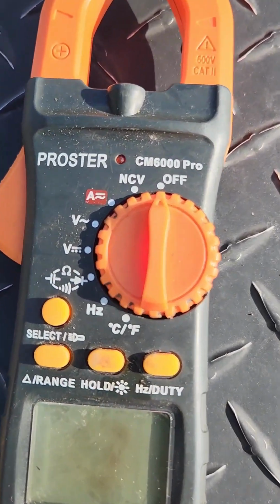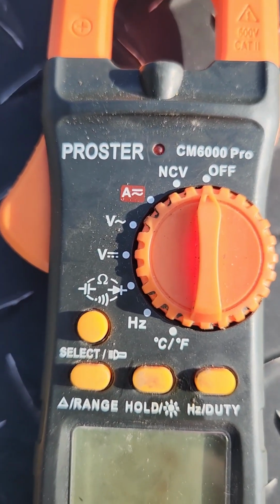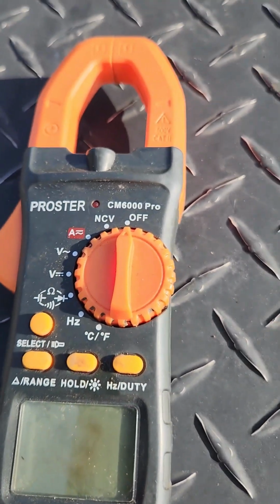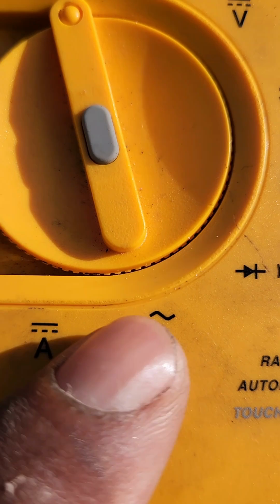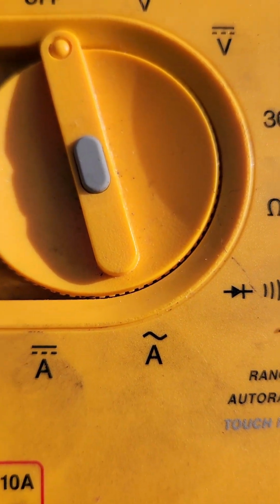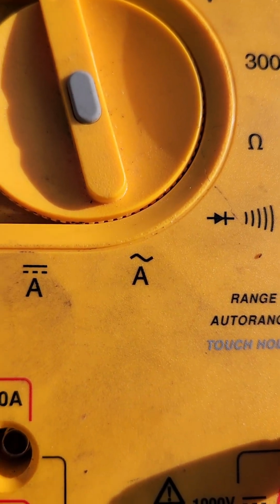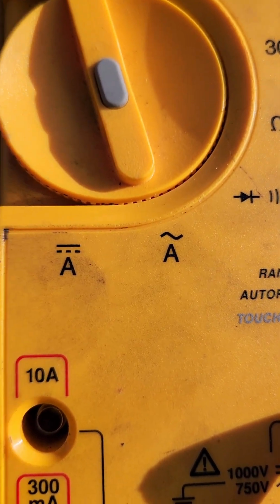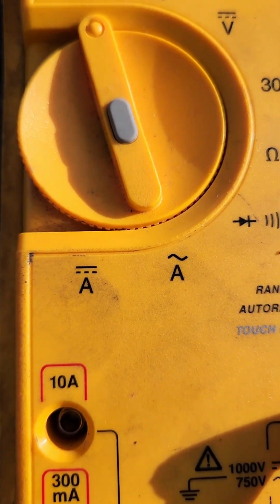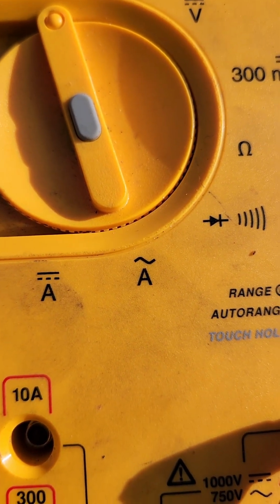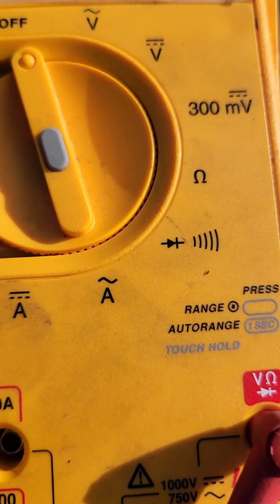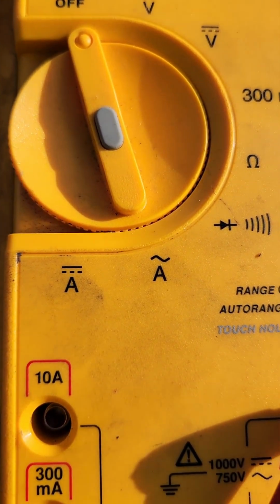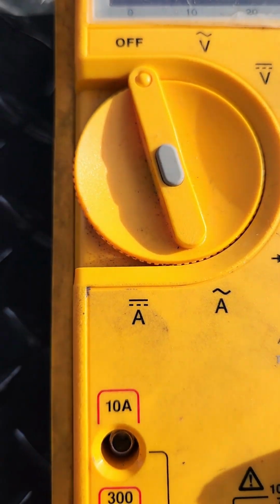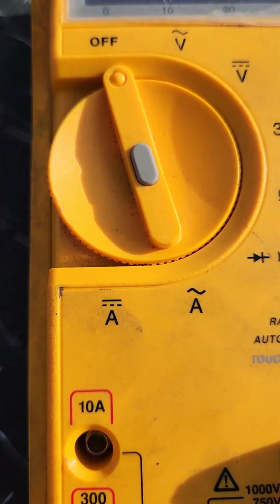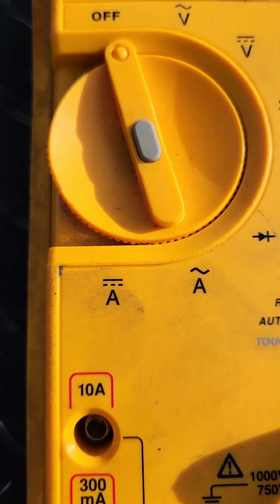The only thing you've got to be very careful about when you buy one is that 90% of them do not do DC amps - normally it'll just have the A with a slant, and you don't want to buy that one unless you're working in a plant with electric motors, pumps, and things like that. When you have a bad electric motor, you clamp it on to check, and on the side of the motor it'll say, like if it's 1 horsepower, 1.8 amps full load amps. So you put the probe on there, and if it says it's drawing 10 amps, that means it's got a ground and the motor's no good. Or if it's not showing anything, the motor's no good.